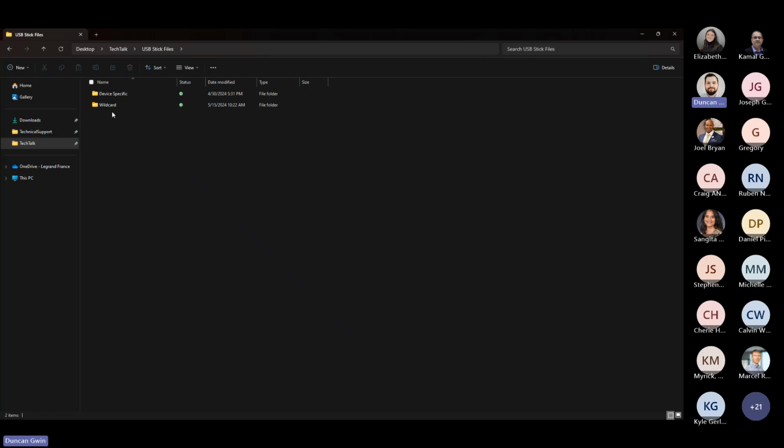We have the wildcard certificate, which I just showed you in the web interface. And what that would look like is we have 3 files that we're going to put on the root folder of a FAT32 formatted USB. We have our cert and our key. Those are the obvious ones. And then the fwupdate.cfg is what we refer to as our control file. So it's the file that the PDU reads when you plug in a USB stick. It's what gives the instructions on what to do and ensures that whatever user is plugging in that USB stick is authenticated to do what they want to do.